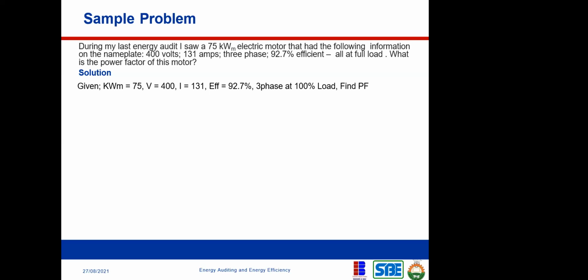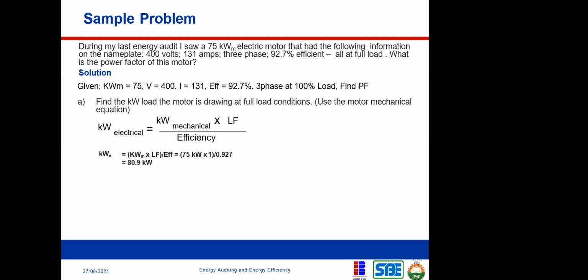Indirectly, they are not asking us to calculate the kilowatt electrical, but there's no way you'll be able to get your power factor if you don't know what your kilowatt electrical is. Are you with me? So now let us first of all calculate what the kilowatt electrical is. The first step is to find the kilowatt load the motor is drawing at the full load condition. So we use the motor mechanical equation.